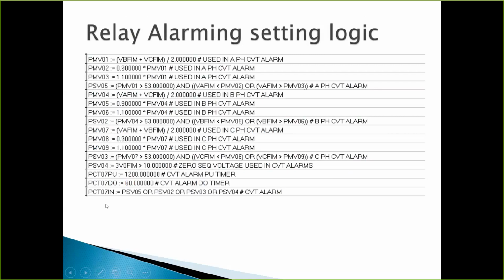So typically we use SEL relays. They're numeric relays. They're easy to set, and we just deploy our logic. So what you do, this is a variable, PMV01. We take voltage, B phase, fundamental instantaneous magnitude, okay? We add that to C phase, fundamental instantaneous magnitude. So we got a snapshot of B phase and C phase. We divide by 2. Hey, that's the average. We take the average of B phase and C phase, okay? We assign that a variable.